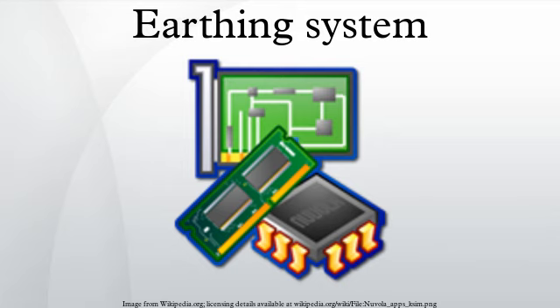Unearthed neutral. In unearthed, isolated or floating neutral system, as in the IT system, there is no direct connection of the star point and the ground. As a result, ground fault currents have no path to be closed and thus have negligible magnitudes. However, in practice, the fault current will not be equal to zero. Conductors in the circuit, particularly underground cables, have an inherent capacitance towards the earth, which provides a path of relatively high impedance. Systems with isolated neutral may continue operation and provide uninterrupted supply even in presence of a ground fault.